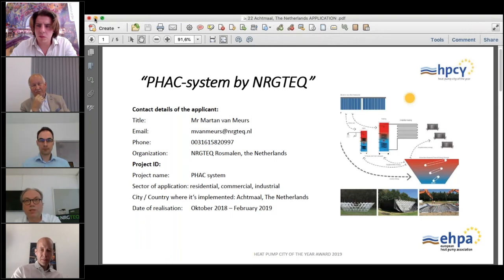The smallest thermal storage put in is approximately 100 cubic meters, which has dimensions of 5 by 5, and approximately 3.5 to 4 meters in depth, and therefore the whole system will be 5 meters high or 4.5 meters high. But as mentioned, you can put it underground and build a parking lot above it. And Phil Shepard is asking, what percentage of the winter demand did the thermal store provide?